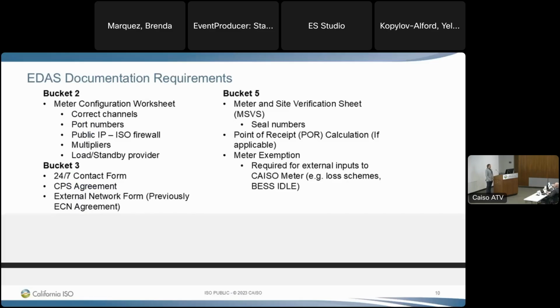For bucket 2, the meter configuration worksheet, some common issues we've seen in 2024: correct channels, port numbers, multipliers. We often get to the test, try to read the meter in, and then there's an issue, where maybe the incorrect number of channels are put in, and we need to do something on the fly to update that. So it makes it easier for us if any changes are made that that updated meter configuration worksheet is submitted to us.